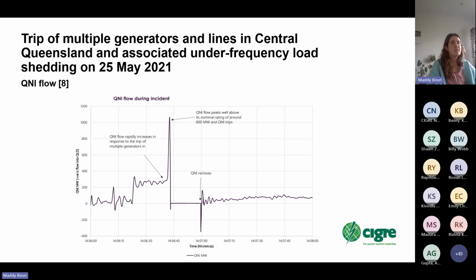So as you can see, due to the loss of all of the different Queensland generating units, the QNI flow into Queensland rapidly increased, peaking at around 1,060 megawatts and then tripped. Usually before the QNI minor upgrade, I believe the import limit usually sits at around a maximum of 600 megawatts.